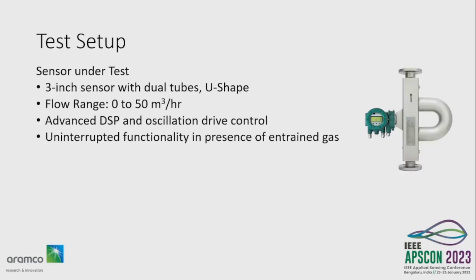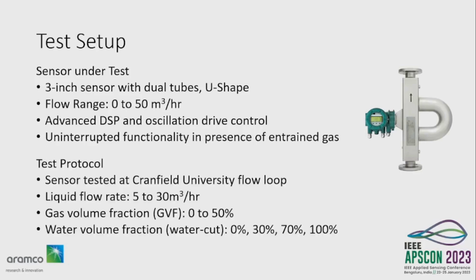What we're trying to do here is understand what sort of errors happen and try to model these errors out of the measurement. We took a standard sensor available in the market that can measure liquid flow rates from 0 to 50 meter cube per hour. It's got some advanced oscillation control and can provide uninterrupted functionality in the presence of gas, but the readings will be wrong, though it does continue to vibrate the tubes and provide measurements.